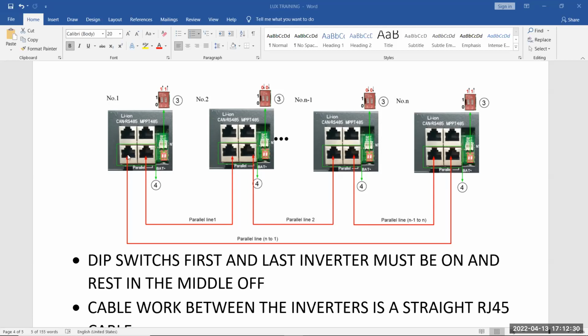Left hand side goes to your furthest inverter's right hand side. So this means if there's 3 inverters, this would go from the first one to the third inverter's last one. If there's 2 inverters, from the first one to the second inverter's last one, and the second one on the first inverter to the first one on the second inverter, if there's only 2. If there's 3 inverters, first one to the last one, from there, the inside one, the second one to the first one, second one to the first one, and then the last one is bounded.